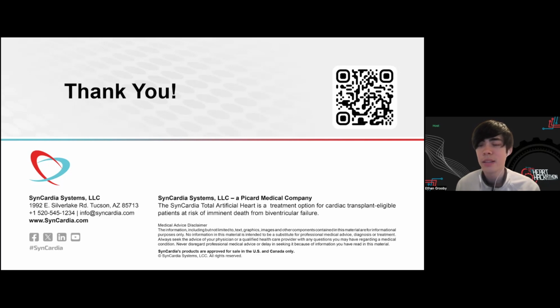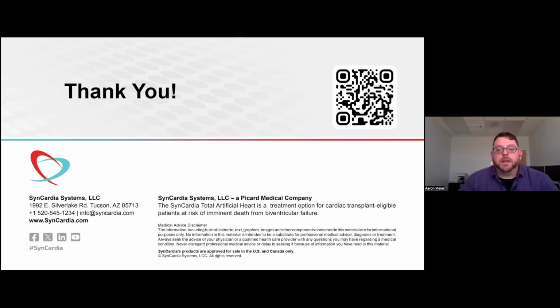Then how long does it take for the FDA to be able to review such quantities of data? I don't have fresh statistics now, but typically a PMA submission takes somewhere from, I would say, 11 to 16 months. So you're typically looking at a year of review.